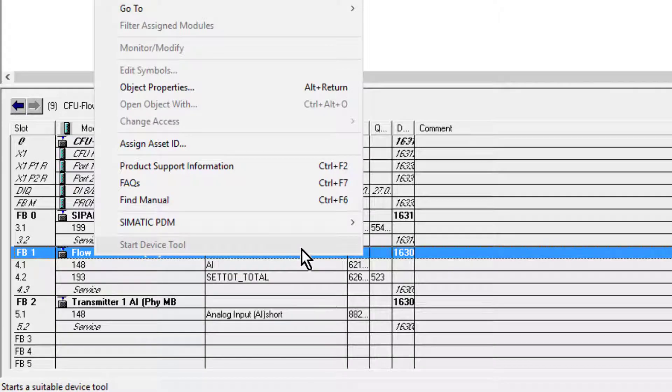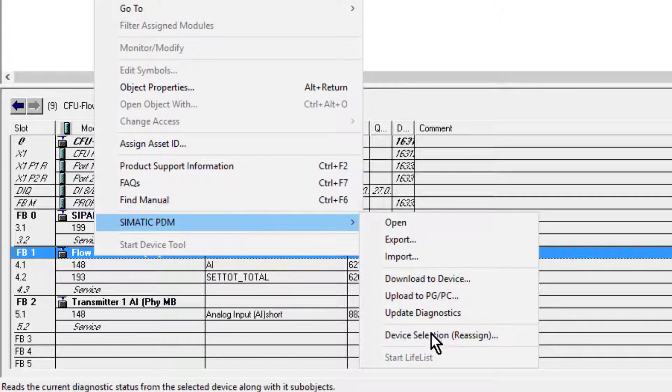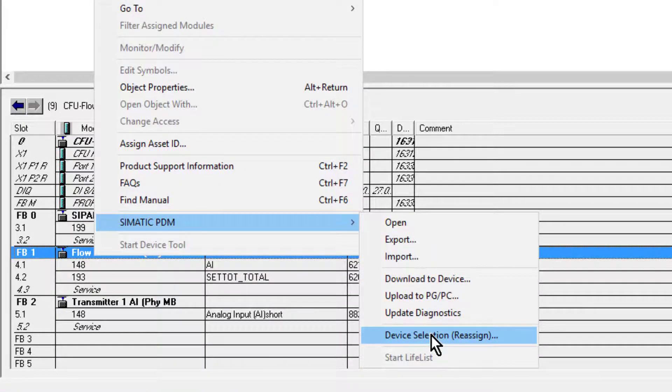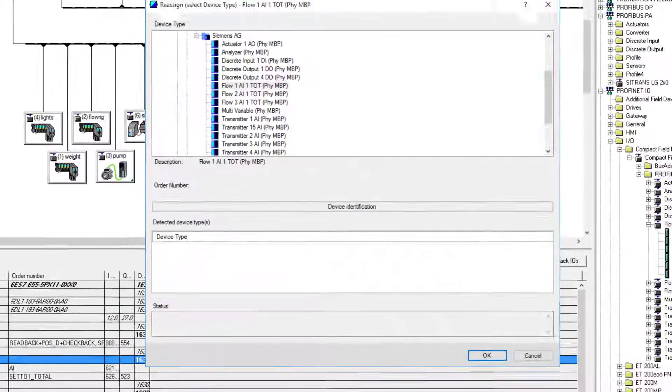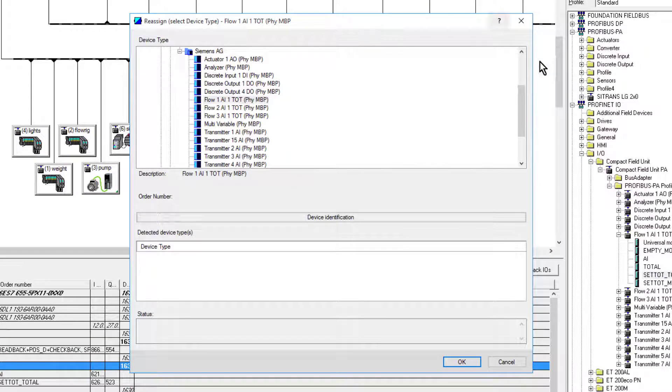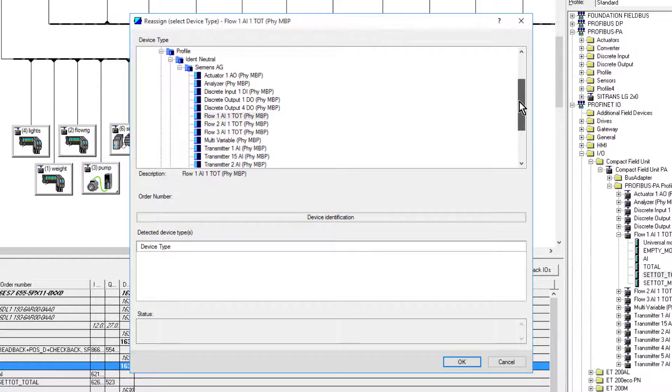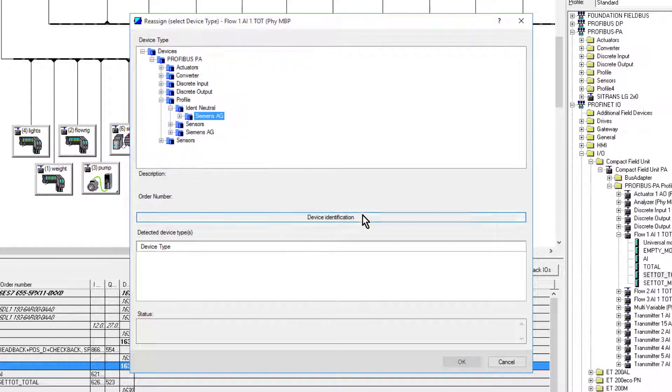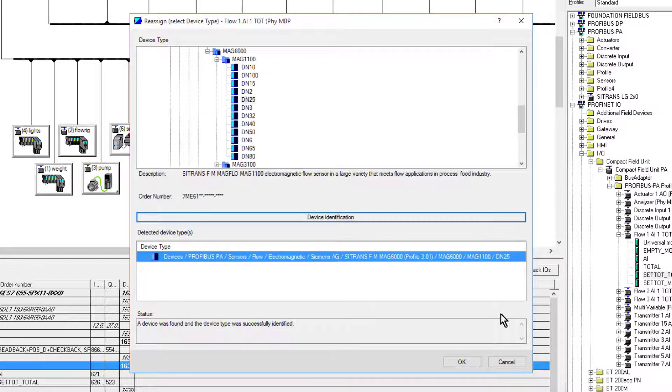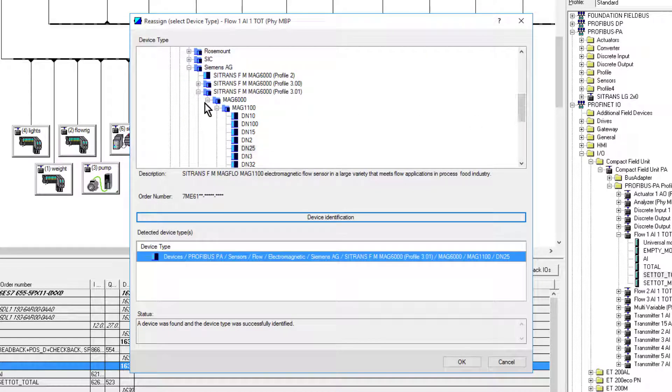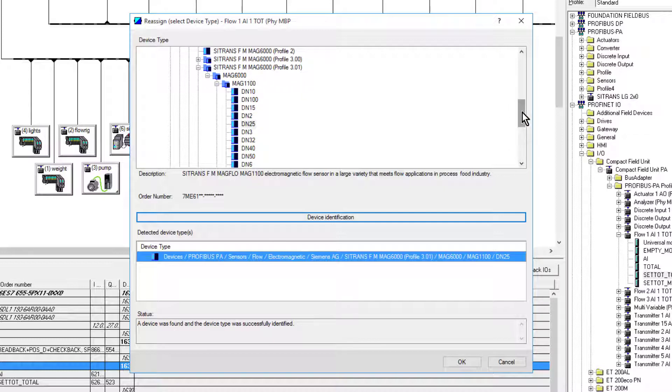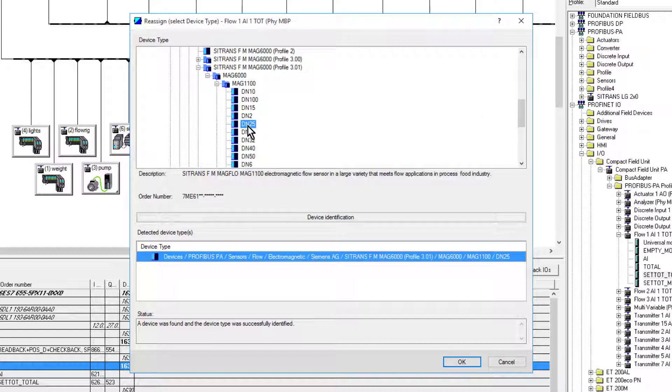So if I have a look here, I can assign my device. Now it's automatically tried to pull in a profile-specific EDD, though you don't have to use that. I can see it's actually found the correct EDD. This is not the GSD that the PLC or automation station uses to communicate cyclically - this is a second channel, if you like, that is used to retrieve the diagnostic information from the instrument.